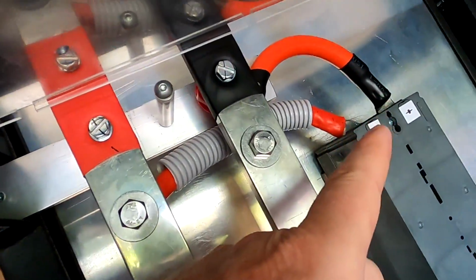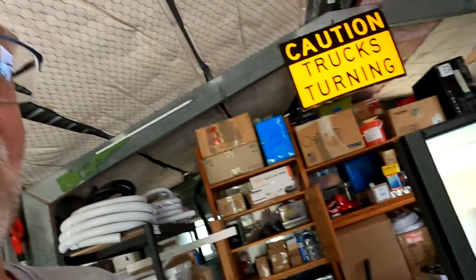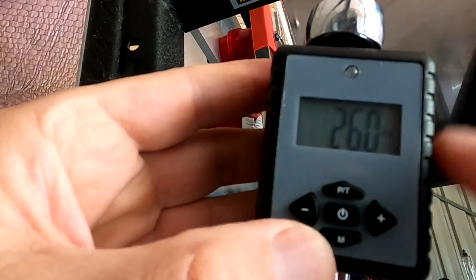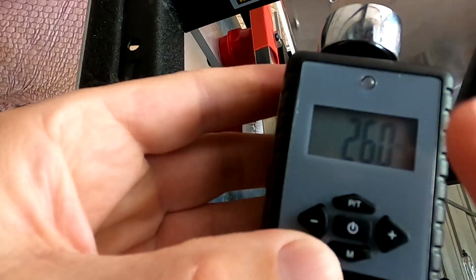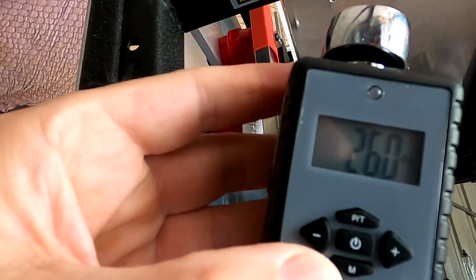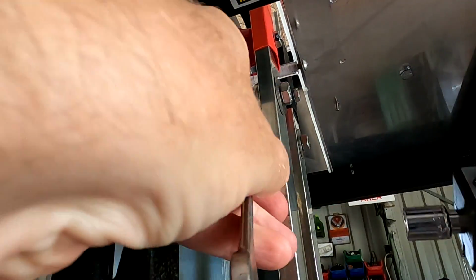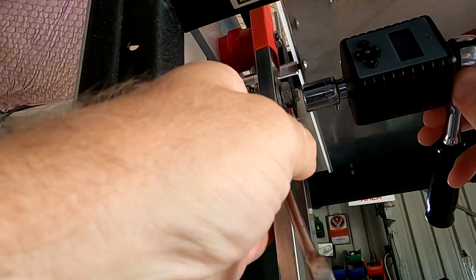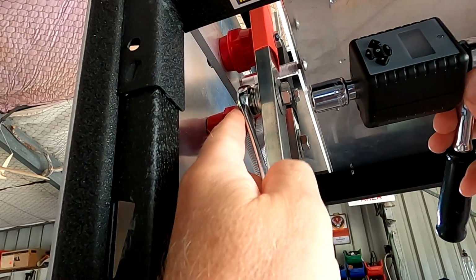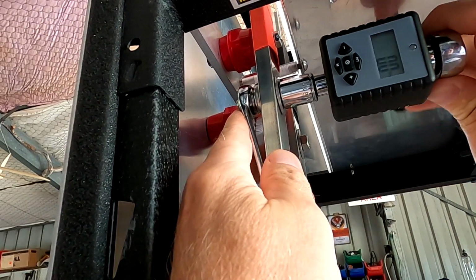And the breakers will have only 6 Newton-meters for the terminal connection, so what's the point, right? Actually, 26 is what I found for zinc plated electrical connections, so 26 it was, not 24—I read too many documents, too many numbers in my head. So 26 it is. Okay, holding this one with a 13 millimeter spanner.